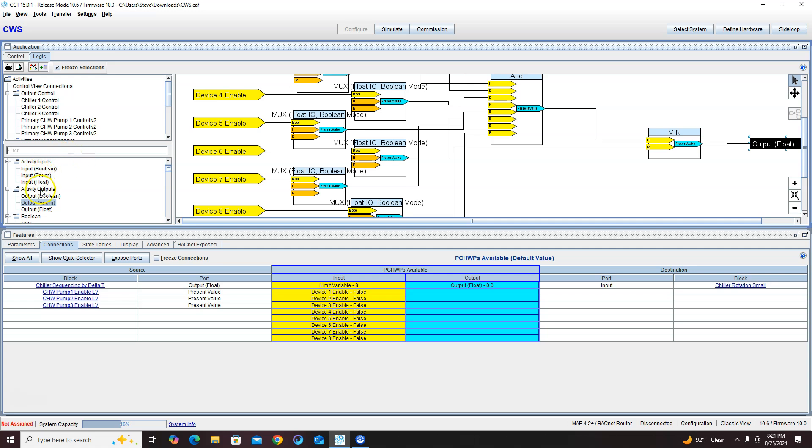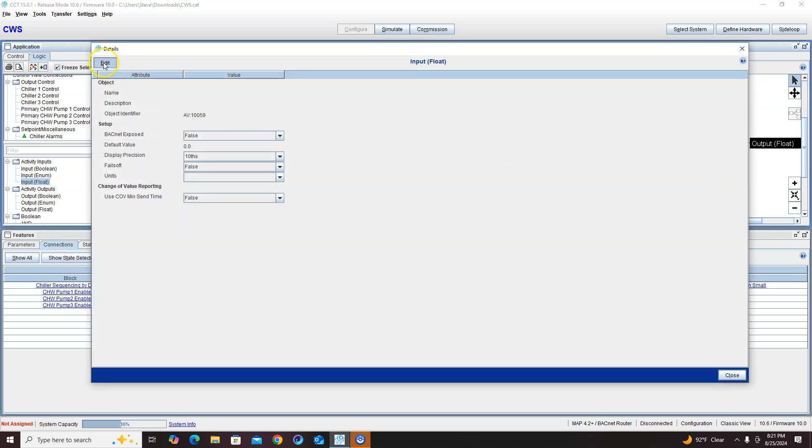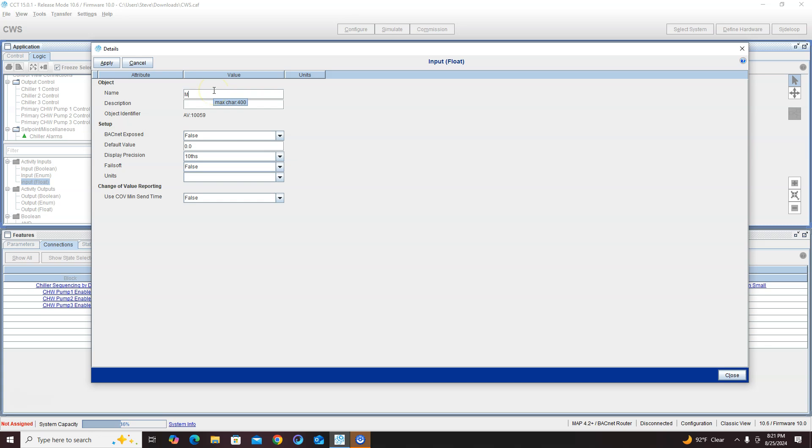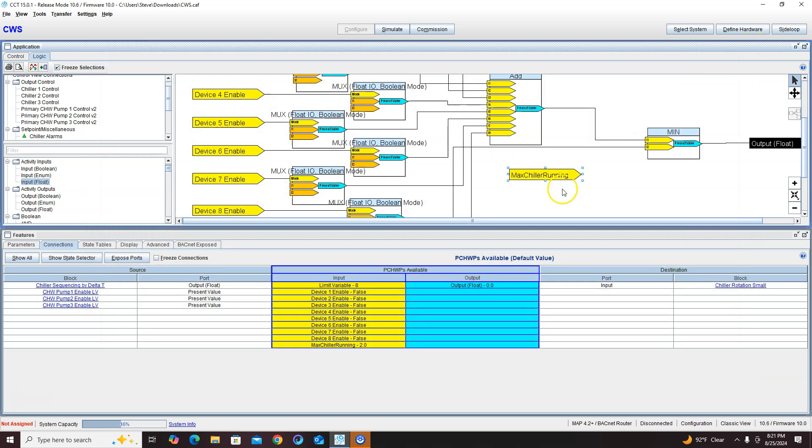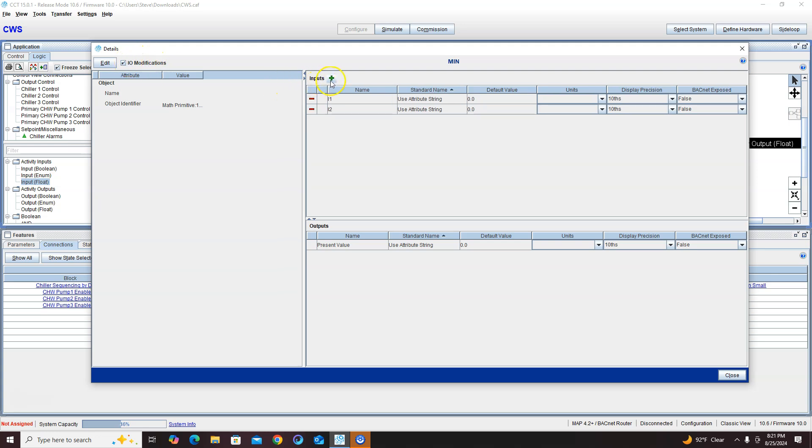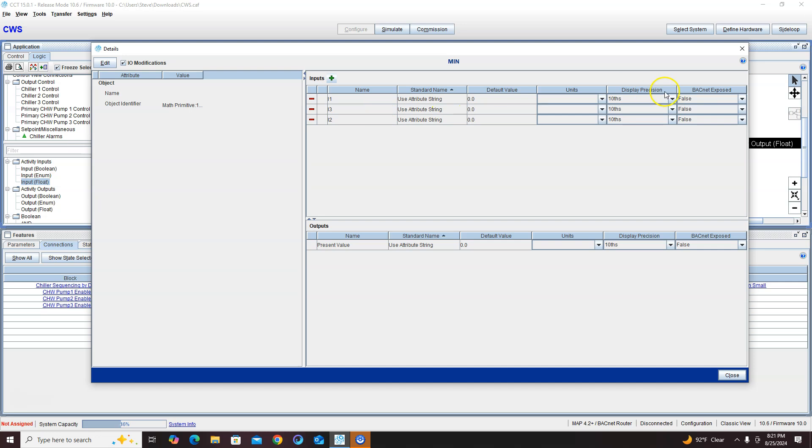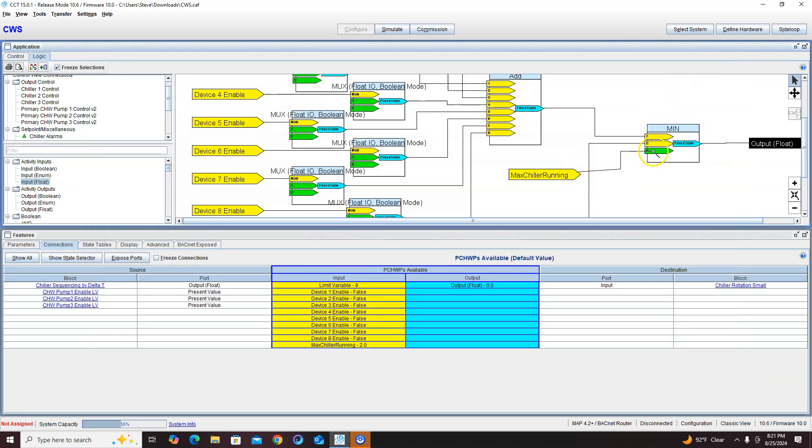Maybe add in a float and call it max chillers running. I'm going to put a default value of two in here, but we can do whatever. And I can add to this min. So now we'll never have more than two chillers running out here because we're going to manipulate this program to only send out a max of two.